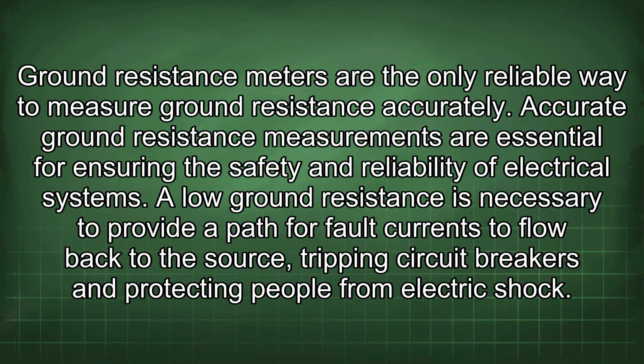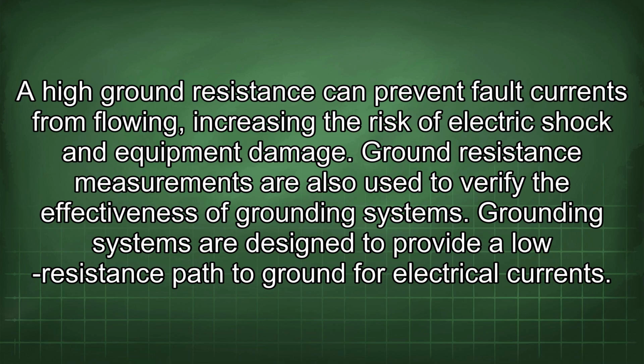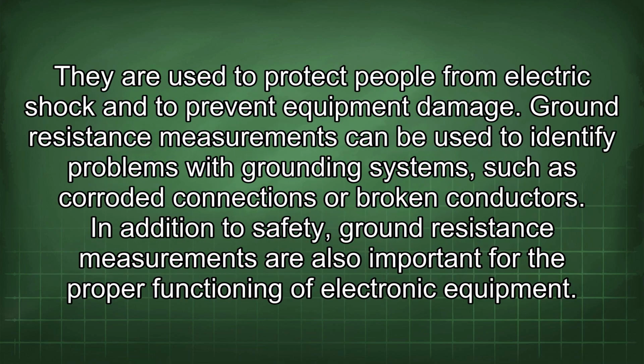A low ground resistance is necessary to provide a path for fault currents to flow back to the source, tripping circuit breakers and protecting people from electric shock. A high ground resistance can prevent fault currents from flowing, increasing the risk of electric shock and equipment damage. Ground resistance measurements are also used to verify the effectiveness of grounding systems. Grounding systems are designed to provide a low resistance path to ground for electrical current. They are used to protect people from electric shock and to prevent equipment damage. Ground resistance measurements can be used to identify problems with grounding systems, such as corroded connections or broken conductors.